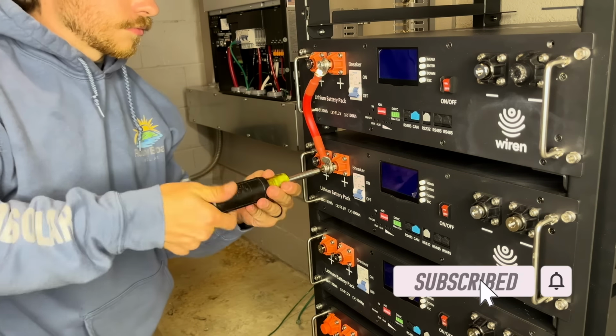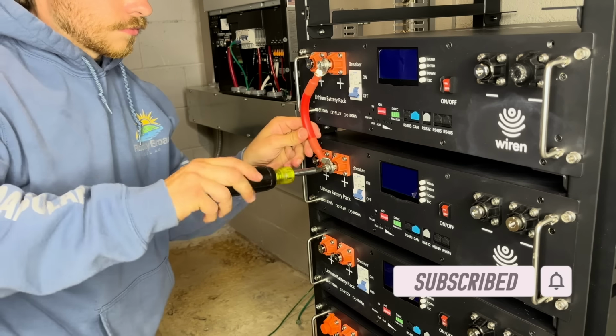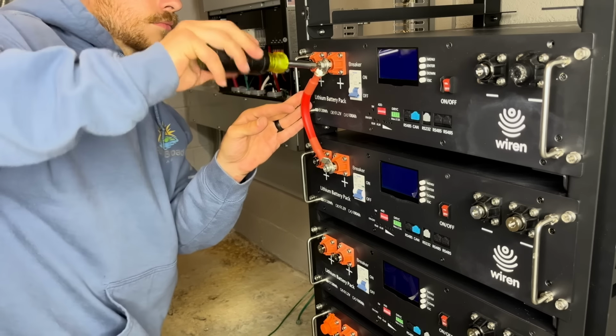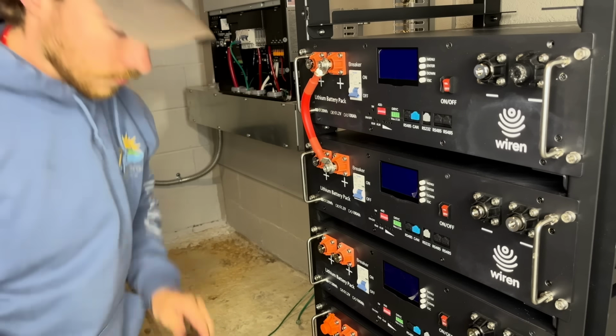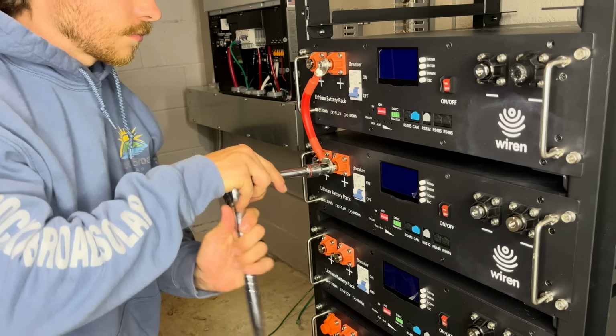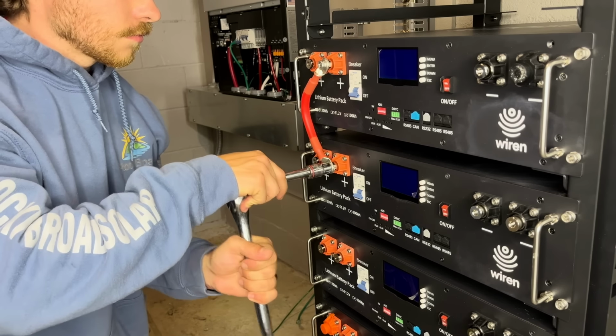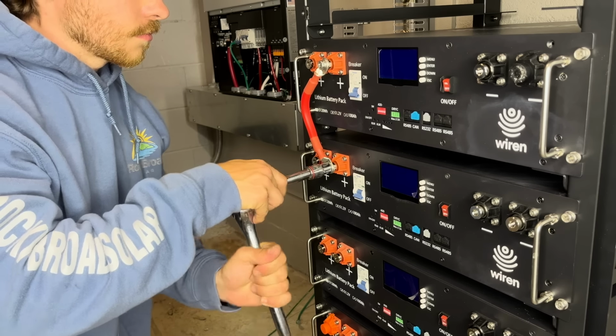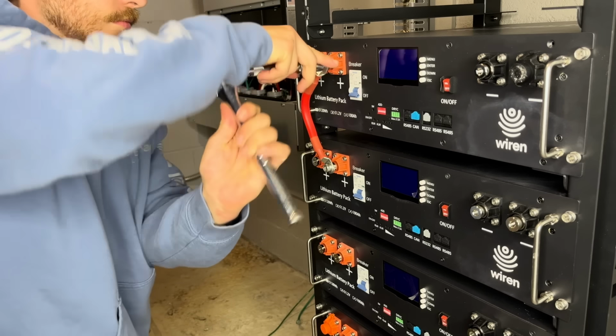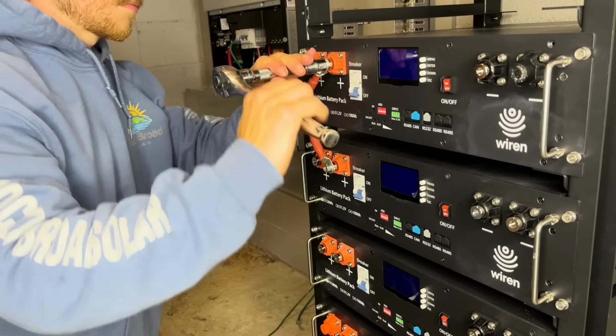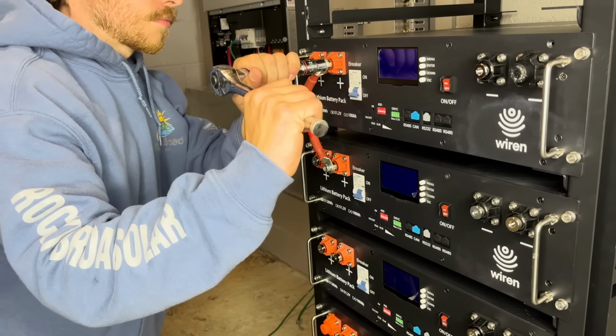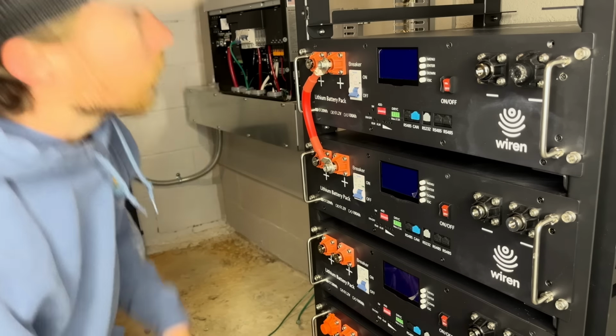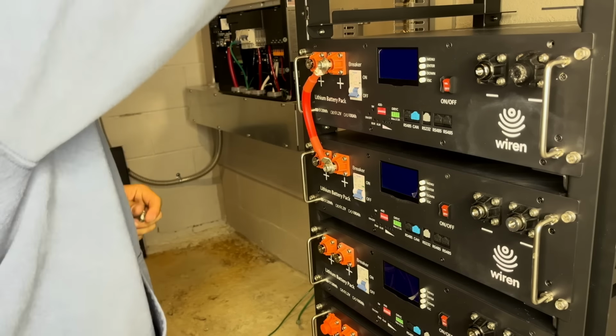Once you get your hands on it, the front layout is what really stands out. Everything you actually need to touch is right there: your DC lugs, your CAN and RS-485 ports, and a status screen that gives you the real numbers - voltage, amps, state of charge, and any faults. You don't have to crawl behind a rack or pull half your gear out just to land a cable or check a reading. You walk up, wire it, verify it, and move on.